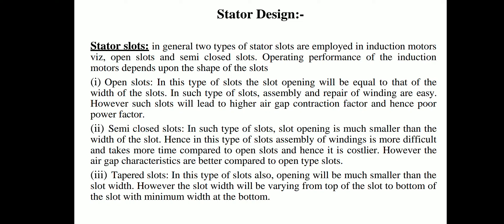In semi-closed slots, the slot opening is much smaller than the width of the slot. Hence assembly of windings is more difficult and takes more time compared to open slots, making it costlier. However, the air gap characteristics are better compared to open type slots.